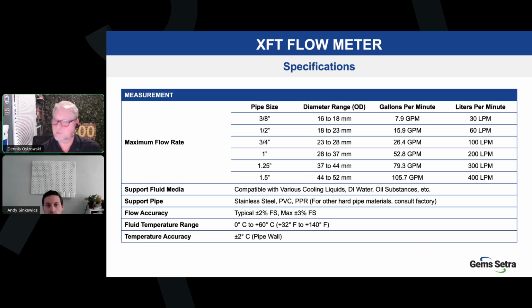The liquid media that are supported, I don't know that it really matters. As long as you know the acoustic velocity, you can look that up online, and you can measure any fluid in that pipe. You do program that into the device, just like the pipe material. You'll choose water-based, oil-based, or other. And again, when you choose other, you'll have to put that sound velocity in yourself and possibly some calibration. The accuracy is typically plus or minus 2% of full scale. You can see a max of plus or minus 3, but typically you're seeing plus or minus 2%, which is right there with all the competition. The fluid temperature range it supports is 32 degrees F up to 140. And the temp accuracy is plus or minus 2 degrees C, and that is pipe wall. So if you want actual fluid temperature, you're going to have your building automation system or your controller or something do that math for you. Okay, next slide.